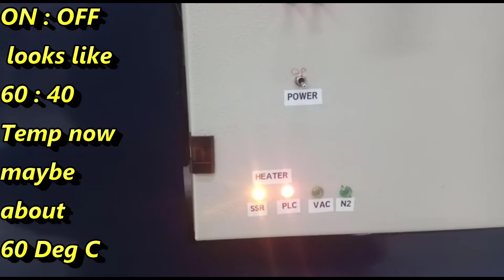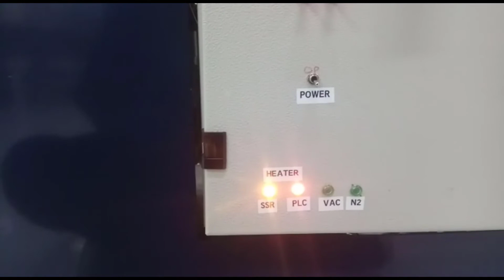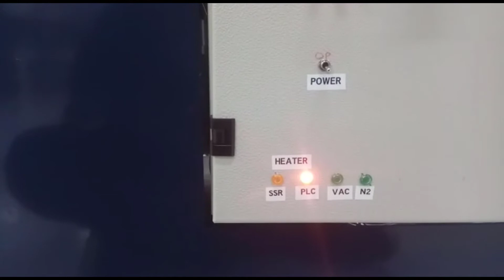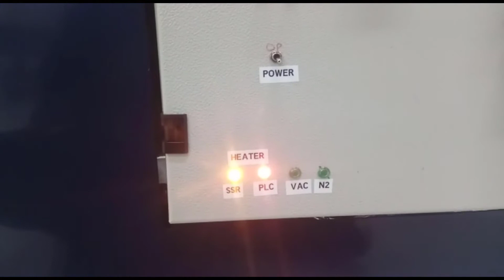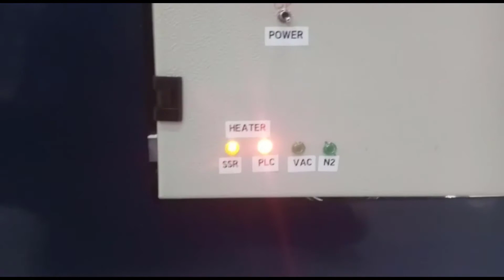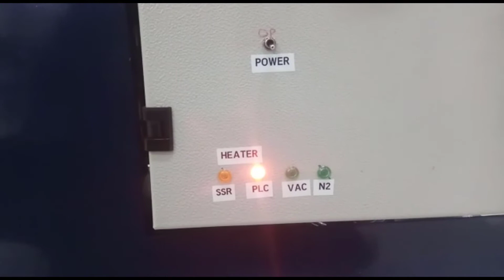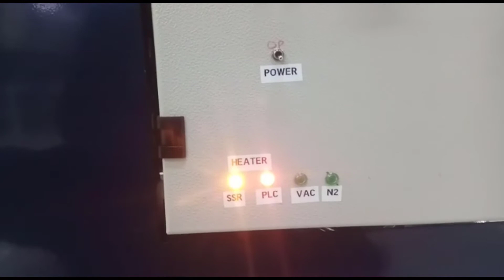So in this mode, at least for this application, and you can do this for any oven for that matter, and any PID controller, you detect what duration it meets when it's near the set temperature. It so happens this is pretty much close to about 8 seconds. So it was decided that an 8-second rule would be pretty nice. When you see an off for 8 seconds, that's a true indication that it has already reached the set temperature, and it works for any set temperature.